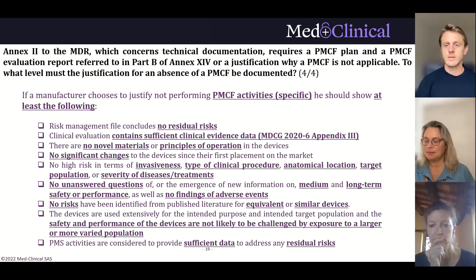Also, you have to see that there are no unanswered questions regarding the medium long-term safety and clinical performance of your device. And there should be also no findings of any adverse events. So once you do your literature search for equivalent devices, if you claim equivalence, or similar benchmark devices, you need to make sure that you did not identify any new risk. Also, another point is that you have to show that your device is only used for the intended purpose in the intended target population, and that the safety and performance of this device is not going to change once it's maybe exposed to a larger or more varied population. So the last point is that the PMS activities should be considered to provide sufficient clinical evidence data to really address any residual risk. So as you can see from all this very long list, it's quite difficult to show all these points. So therefore, I think it's rather possible for low risk medical devices here.